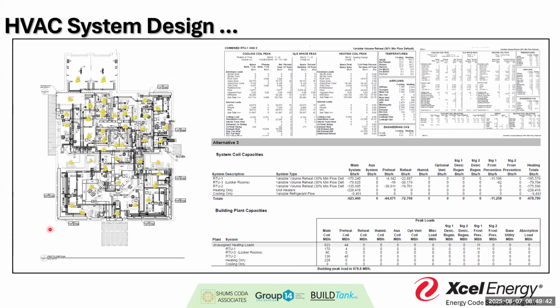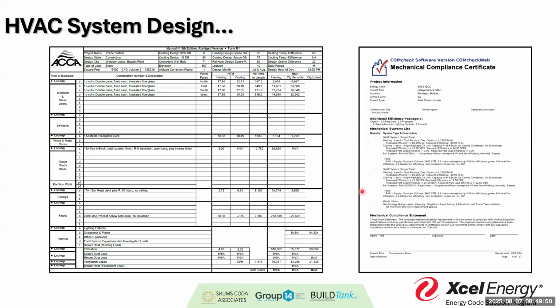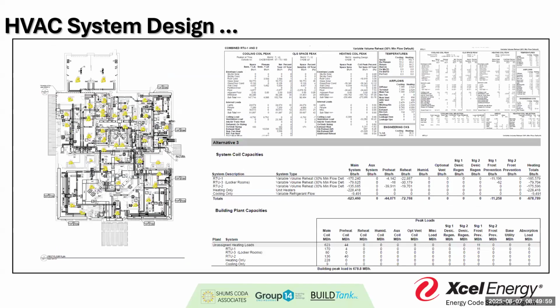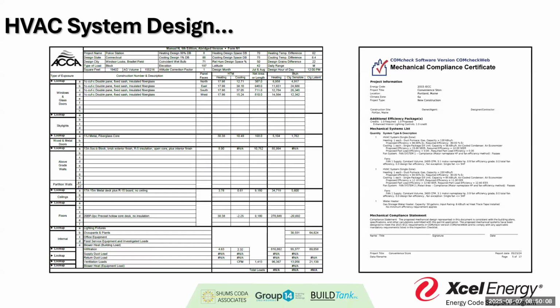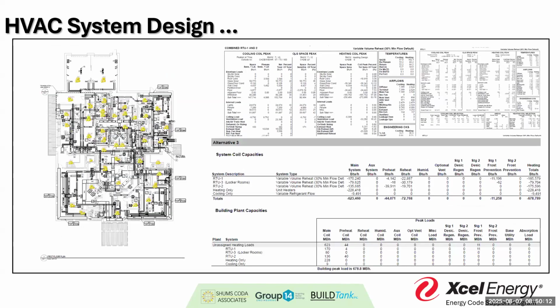I can verify that we've got different equipment identified. I see here 3 different RTUs, but when I go back to my ComCheck, I only saw 2. So I'm going to ask: what happened? I see 2, and then I see 3. What they'll tell me is, oh well, we installed that later, that's a separate unit. Then this ComCheck is now almost useless to me. I'll use it to evaluate those 2 components, but other than that it's useless.